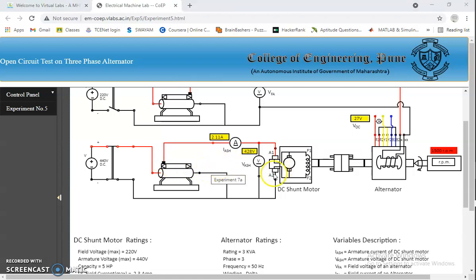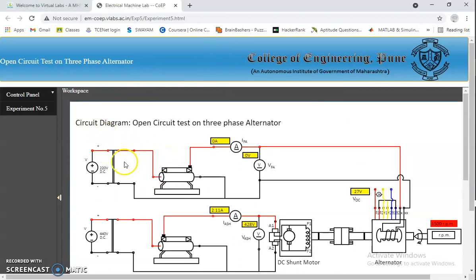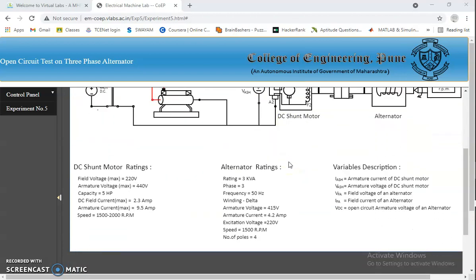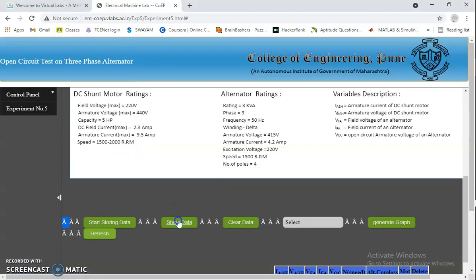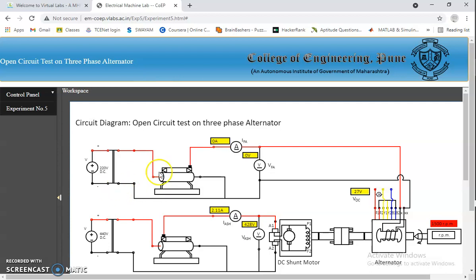Next, we have to excite the rotor part. In order to produce constant magnetic flux, we are giving 220V DC supply by closing the switch. By adjusting the field rheostat, we need to bring the alternator to its rated voltage or no-load voltage. At the same time, we need to start storing its data and need to click show data.